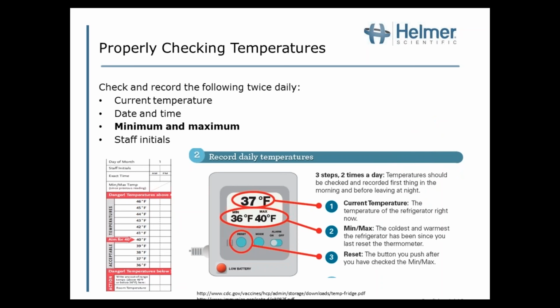So even though we have continuous monitoring of temperatures and we can download reports, and when there is an excursion we of course need to see exactly how long it's been out, I think it is a CDC recommendation, and I think it's really important, I'm glad they left it in there, that we need to continue checking the temperatures ourselves. The CDC recommends twice daily temperature readings, which is another common miss I see. I oftentimes see temperature logs that only allow you to record once a day, and staff that might only be recording once a day. And so we're going to need to record the current temperature, the date, and the time. And again, the time is important because of the case there's a temperature excursion. We need the minimum and maximum, and then finally we need the staff initials.